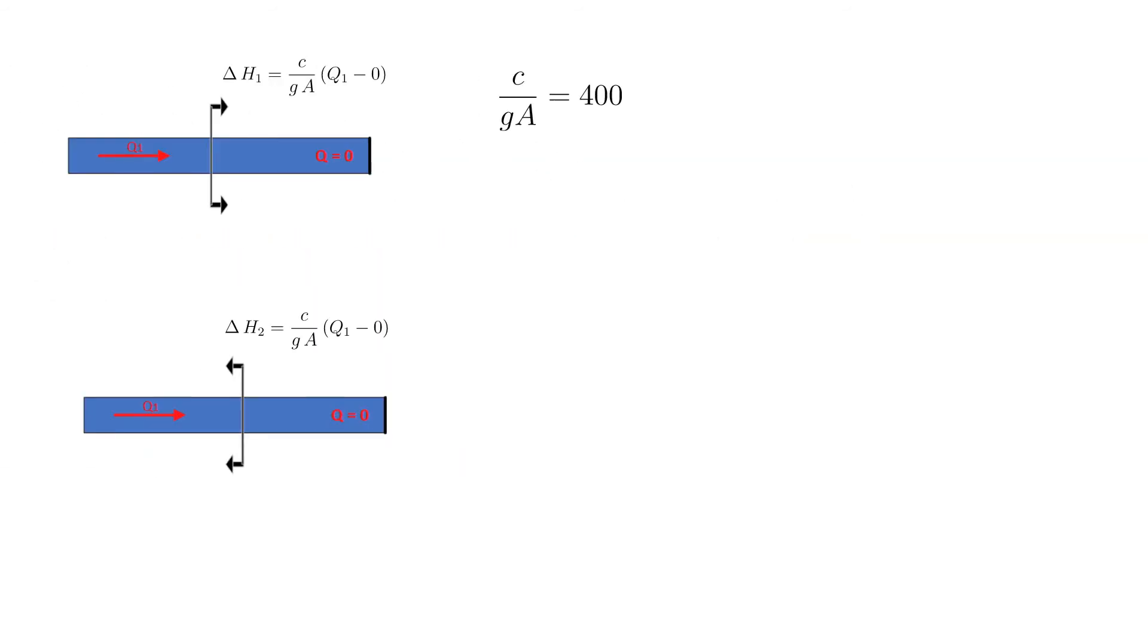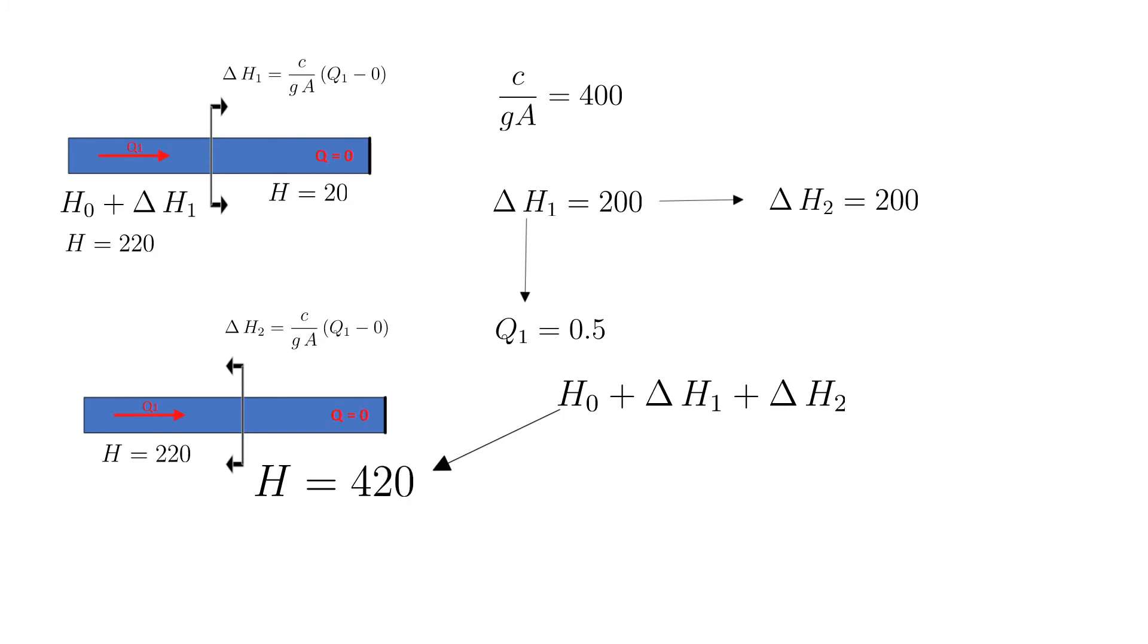Let's add some numbers to provide additional clarity. The initial head is 20, the incoming wave is positive 200. The flow behind the incoming wave Q1 is 0.5. The head behind the incoming wave is 200 plus 20 or 220. The incoming wave reflects off of the dead end with a value of positive 200. The flow behind the reflective wave remains zero. The head behind the reflective wave is the original head with the incoming and reflected waves added. In this example, the head behind the reflected wave is 420.